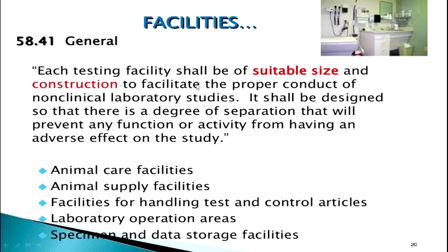It is also very important to see that the equipment you are using in the lab is mounted on a proper mounting, because some equipment will produce heat, some will produce vibration, and some may produce noise. So are they mounted on a proper platform if they have vibration? If heat is being generated, what precautions are taken? If noise is being generated, what sound regulations are you following? Even that falls under the facilities. And where these equipments are placed, what is the spacing of one equipment to another, whether they are being followed, and whether your lab is under a particular spacing.